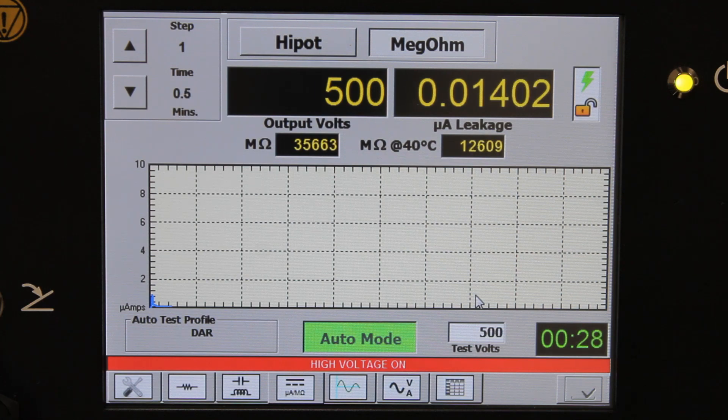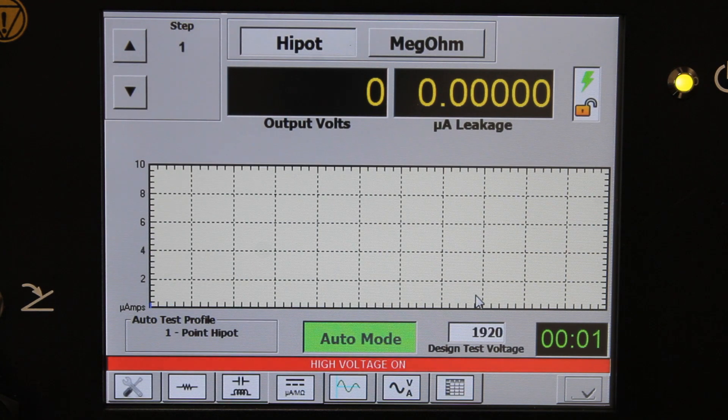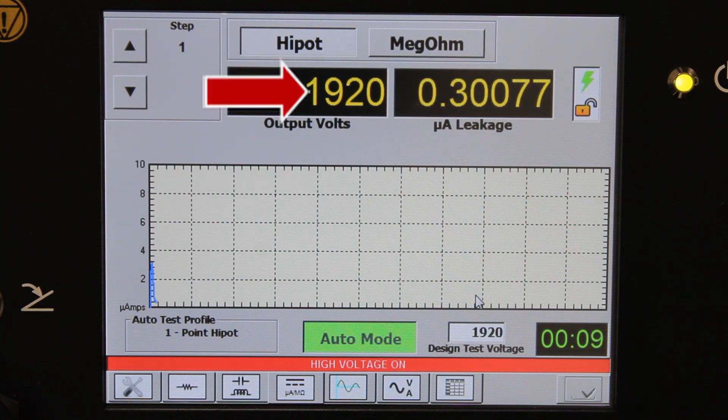If we exceed the predefined 5 megaohm minimum value, we're going to move on to the DC Hypot test. We got a DAR of 2.12 and exceeded the minimum requirement, so we're now on to our Hypot. The instrument brings the voltage up to 1920 volts automatically, and we're going to sit here for one minute and measure the leakage current.